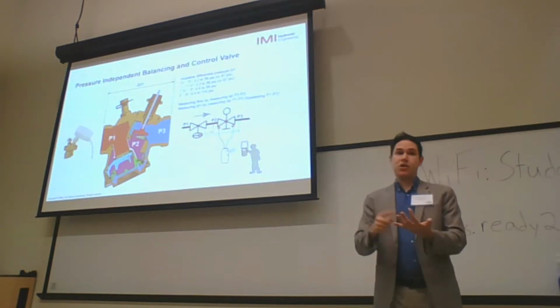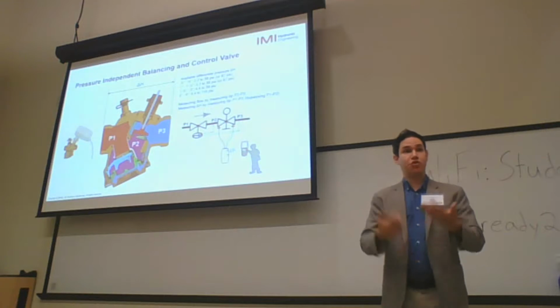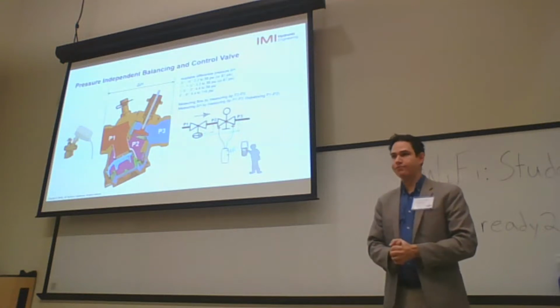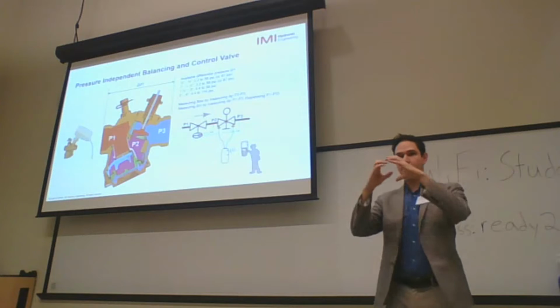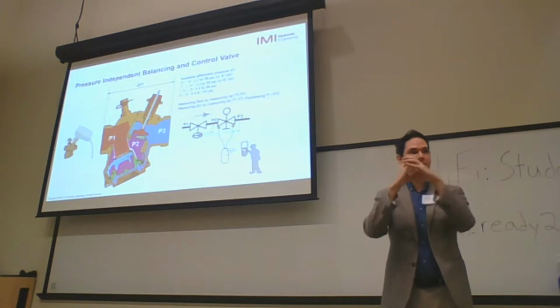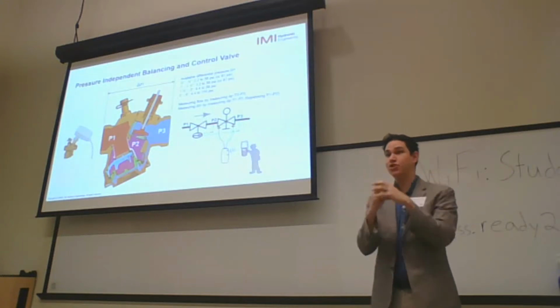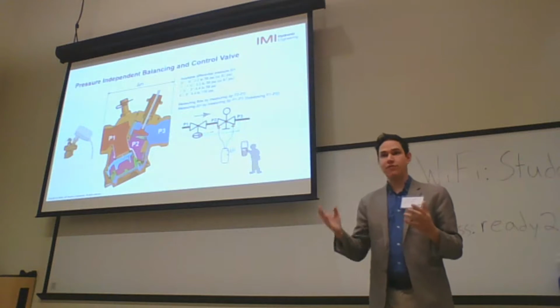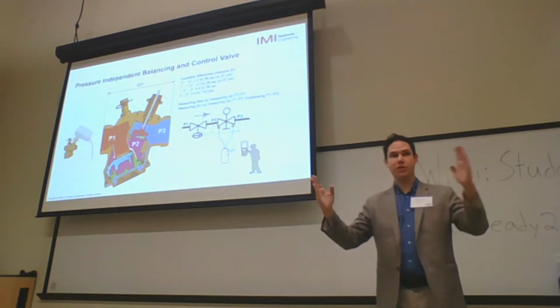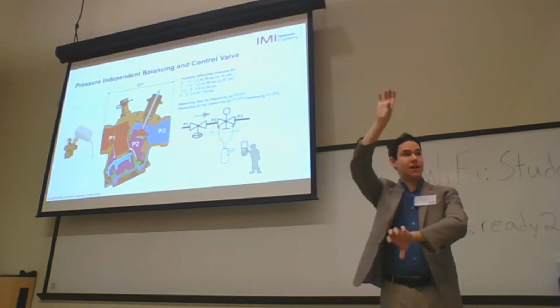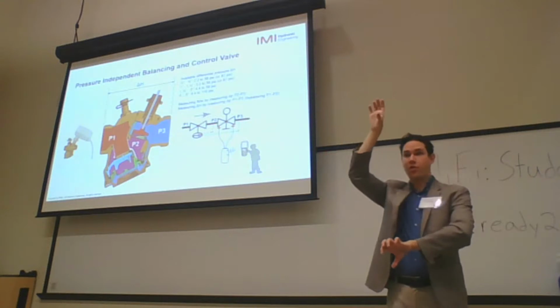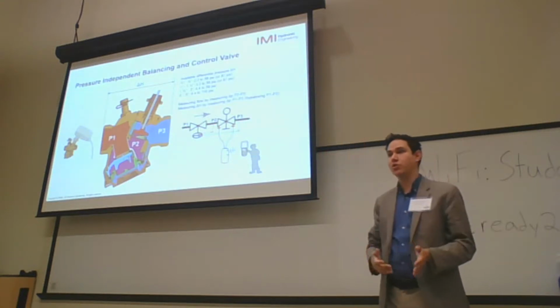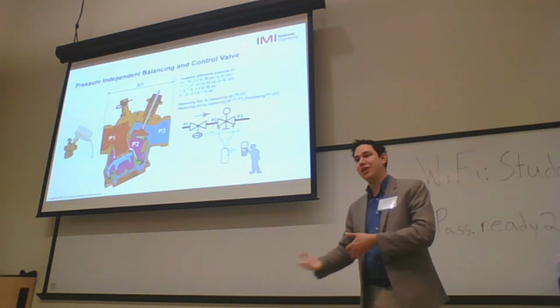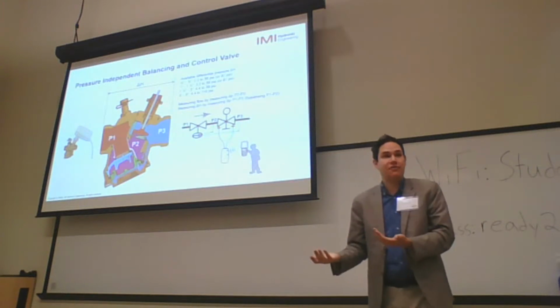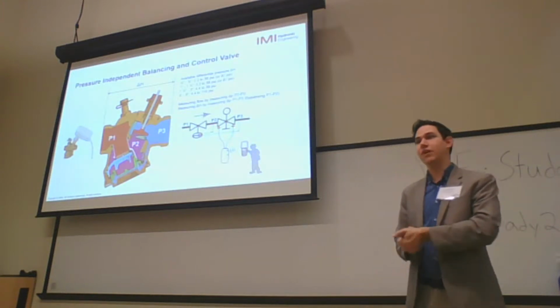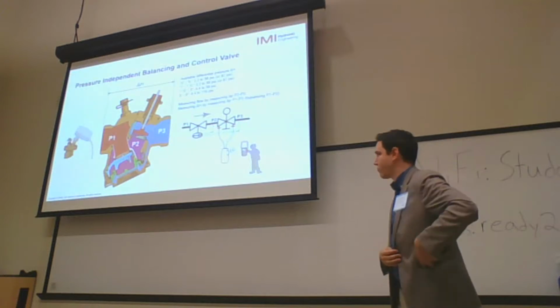You can find clogged pipes. If you're troubleshooting a really old installation and you're unsure about the condition of the pipe, with all the dirt and all the changes in the pipes, if you measure the available pressure between the two points, you can find exactly the pressure drops on these pipes and compare them to the real pipe or new pipe pressure drop. So this is the advantage of measuring the available pressure in the installation.